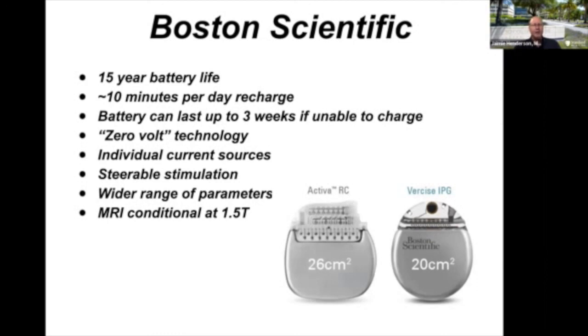Another nice feature of this is that it has what's called 0-volt technology, which means that if it completely discharges for whatever reason, you can always wake it back up and get it started again. Sometimes if you deep discharge a battery, it won't work. So Medtronic's rechargeable system, if that happens to it, it's dead and you have to replace it. Whereas the Boston one, you can wake it up if you ever get to the point of it completely discharging.